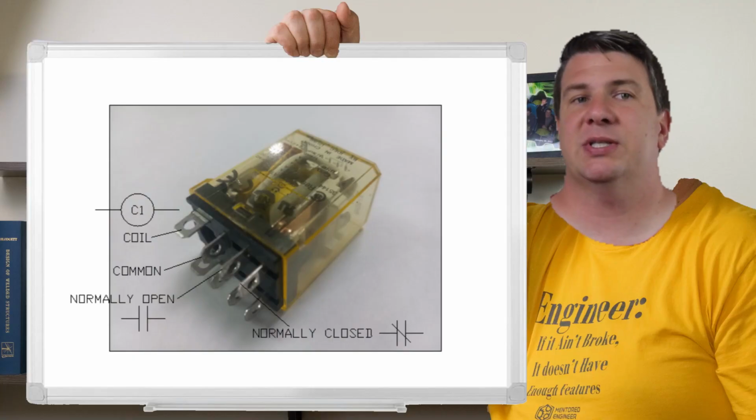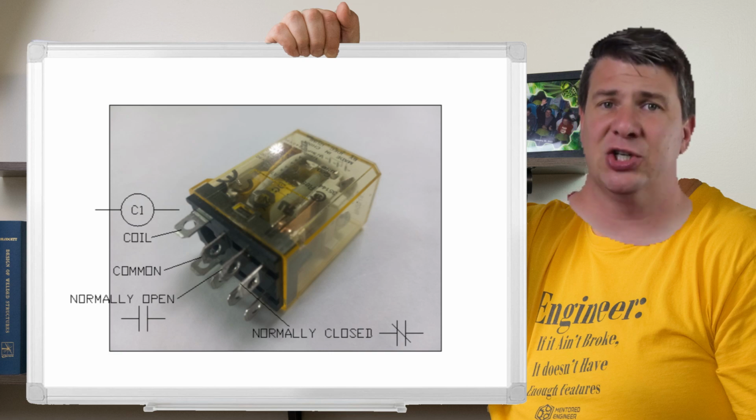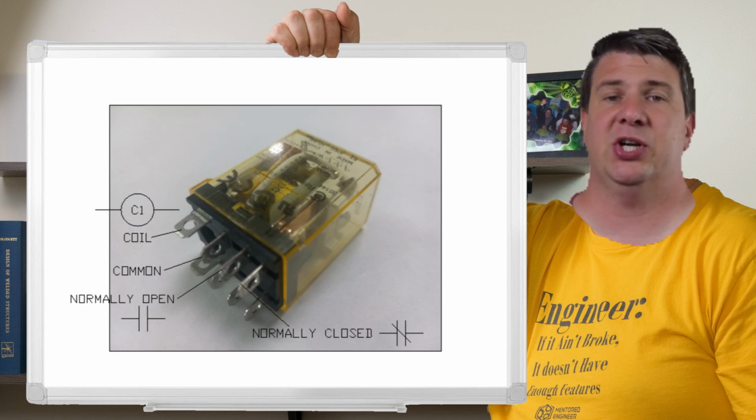So we're going to have this, where the light switch is connected to the left rung, and then the output of that switch is going to be connected to the lights, and then the lights connected to the 0 volt rung. First wrinkle here is we got a relay in that circuit, so we actually have to divide that into 2 rungs. So any relay is basically an input side and an output side. So the output side is going to be the coil. That is what we energize to get the inputs to change.